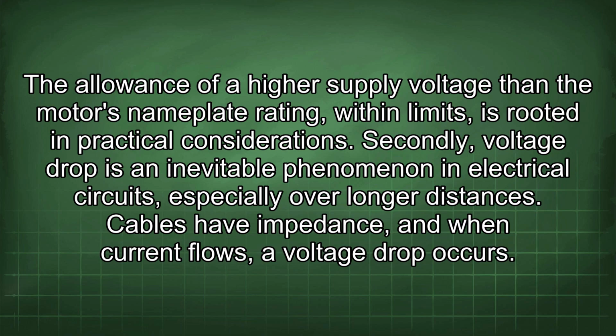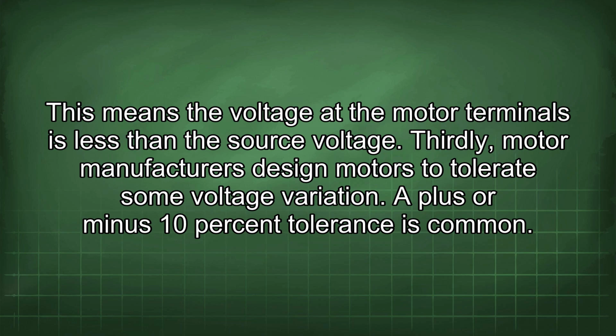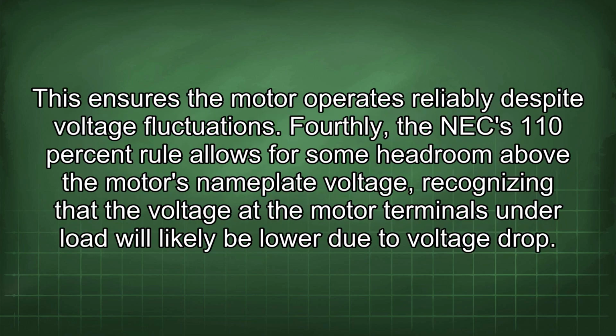Secondly, voltage drop is an inevitable phenomenon in electrical circuits, especially over longer distances. Cables have impedance, and when current flows, a voltage drop occurs. This means the voltage at the motor terminals is less than the source voltage. Thirdly, motor manufacturers design motors to tolerate some voltage variation. A plus or minus 10% tolerance is common. This ensures the motor operates reliably despite voltage fluctuations. Fourthly, the NEC 110% rule allows for some headroom above the motor's nameplate voltage, recognizing that the voltage at the motor terminals under load will likely be lower due to voltage drop.